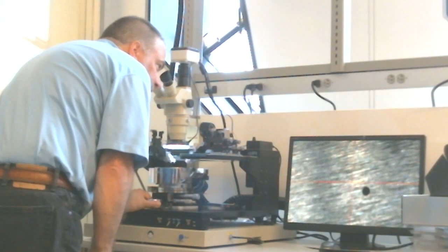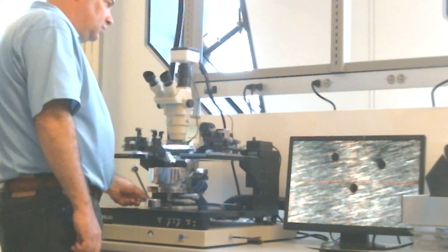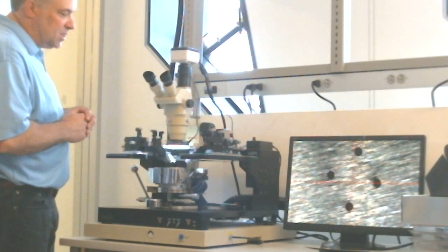Basically, I'm looking for 4 vacuum holes in the center. When you put the switch in the on position, it'll activate those 4 vacuum holes. So if you're doing a single sample or a small single die, the best place to do it is right there in the middle. Turn your vacuum switch on, and you've got vacuum just in those center holes.